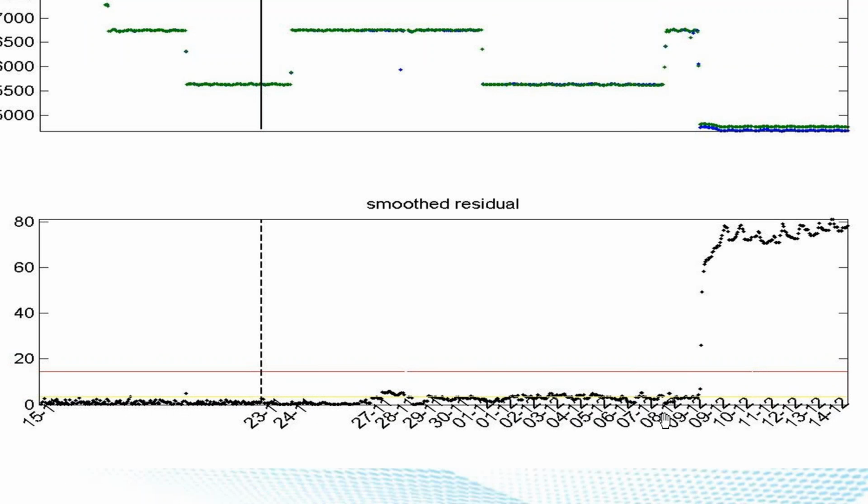We actually identified the problem. We saw that this was inner corrosion, which is very easy for us to identify. Our algorithm is so sensitive, we can actually sense that the inner diameter of the pipeline is getting bigger. The corrosion eats the pipeline from the inside. It's a very slow process, and it's very difficult to detect because it eats very small amounts.